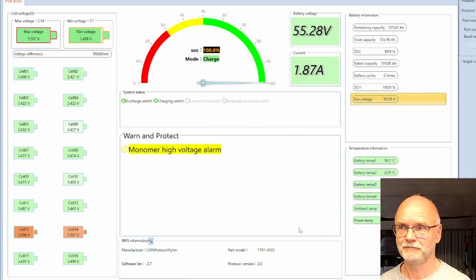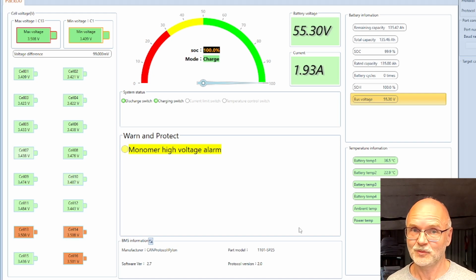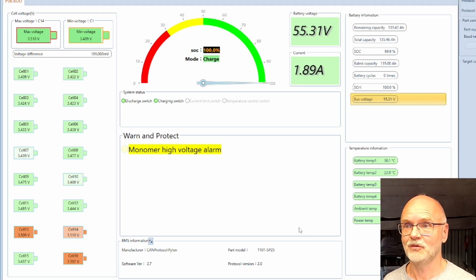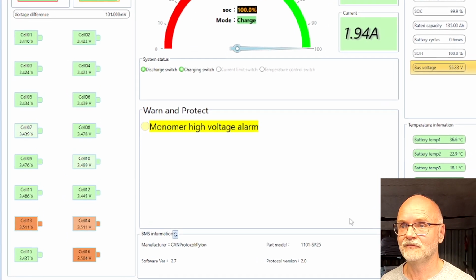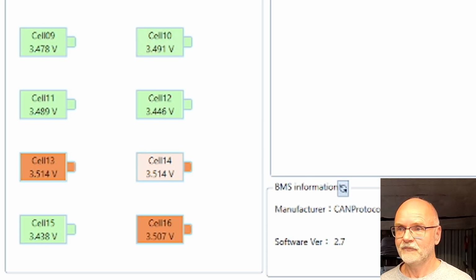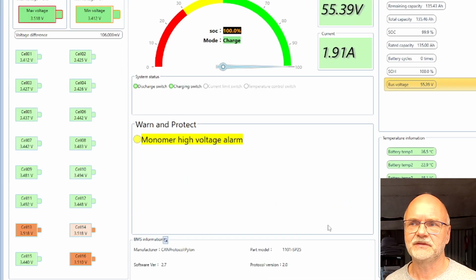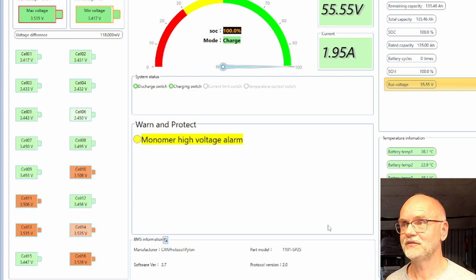We are now at 55.2 volts, which means 3.45 per cell if they were 100% balanced. Even recharging them to 3.6 volts with a 1 amp cutoff doesn't fully balance the battery pack, obviously. You can see cells 13, 14 and 16 have already passed 3.5 volts, and we get a high voltage alarm for the single cells. But cell number 1 is only at 3.4 volts, and we've got a 117 millivolt deviation now at 55.5 volts.